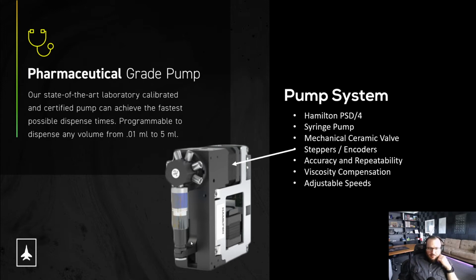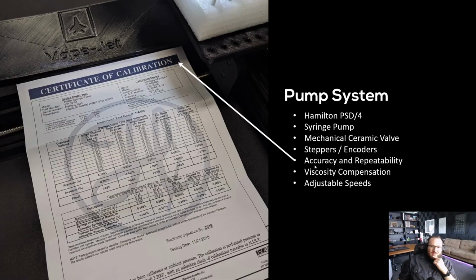Both the syringe pump and the valve are controlled by stepper motors and encoders. The encoders are important so that we can measure the physical position that the valve or the syringe is in, not just what the software tells the stepper motor to go to. And the reason that's important is for our viscosity compensation.